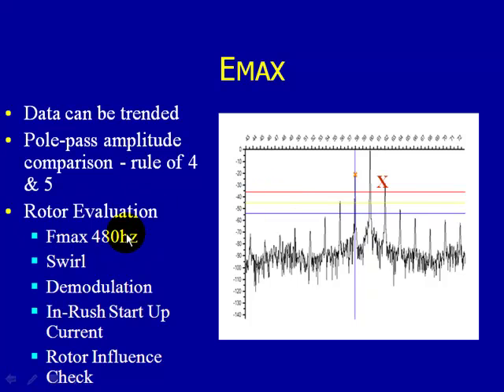We want to utilize every tool available in the E-MAX, going out to 480 hertz, which allows us to use our swirl or look at our fifth harmonic. The fifth harmonic is essentially a phase shift in the air gap flux on the rotor, which creates pole pass frequencies around the fifth harmonic that we monitor for. We also utilize demodulation, which filters out the 60 hertz signal, leaving behind mechanical anomalies in the demodulation spectrum. This can also be used for very accurate two-pole rotor bar analysis.